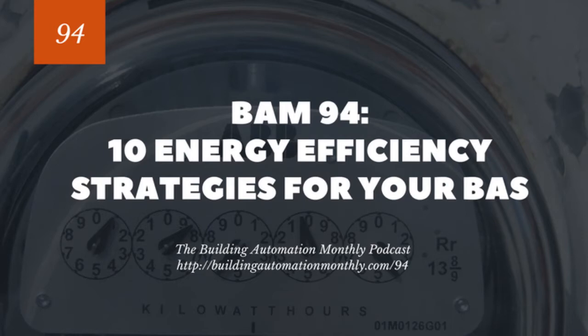Now, way number 3, we talked about this in previous episodes, but you really want to avoid using overrides as much as possible. Whenever possible, use timed overrides. Do not use actual static overrides. And what is an override? That is when a point is being commanded to a certain value. Maybe it's a valve, maybe it's an on-off for a fan, and you override that value. You want to avoid any overrides as much as possible.